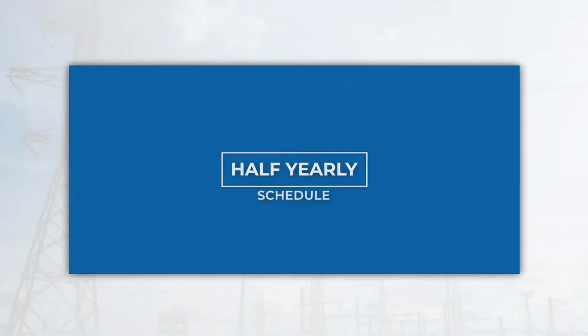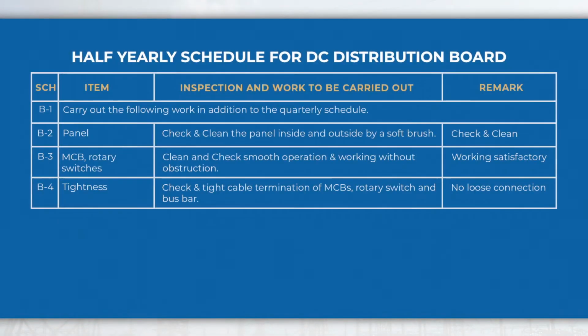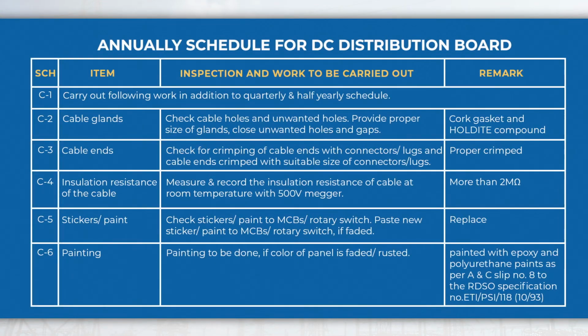Half-yearly schedule. In the half-yearly schedule, perform activities like checking of all cable termination and smooth operation, including working of MCB and rotary switches, etc., in addition to quarterly schedule activities. Annual schedule: in the yearly schedule, perform activities like measuring the insulation resistance of cable and checking all cable termination, crimping of cable ends with connectors, lugs, etc., in addition to quarterly and half-yearly schedule activities.